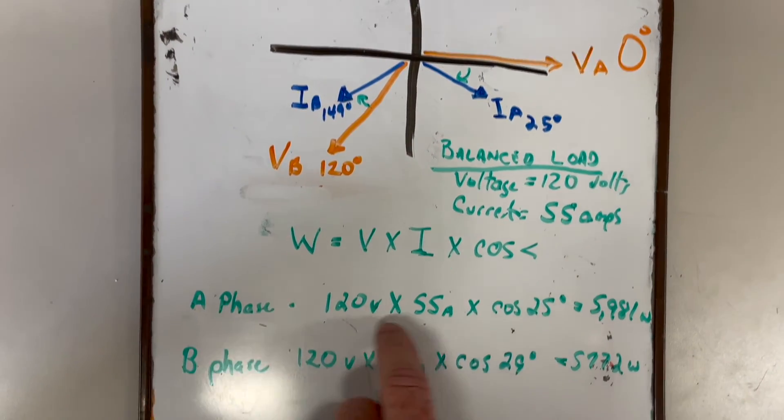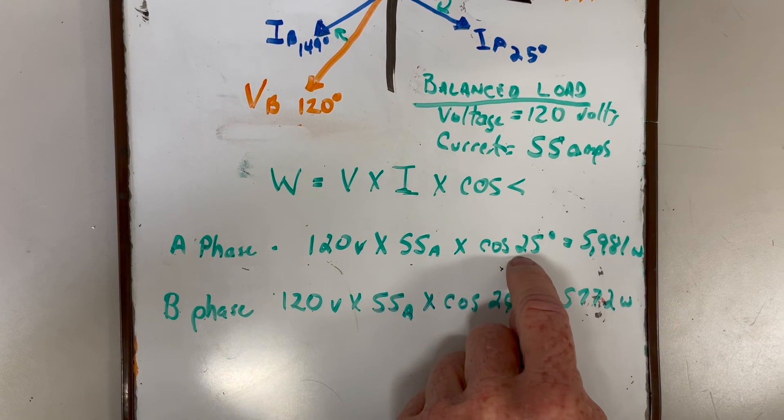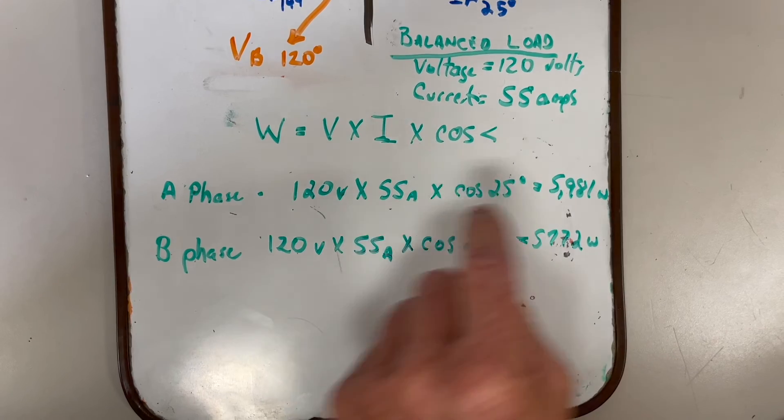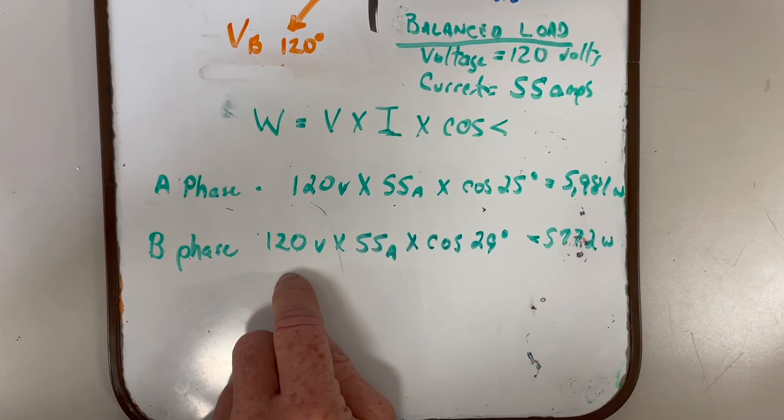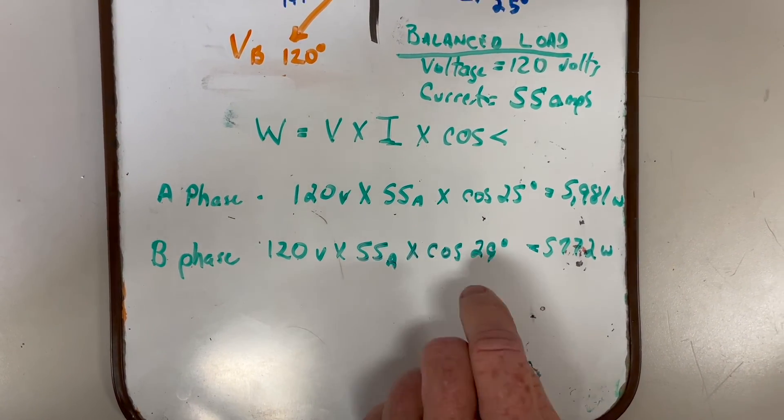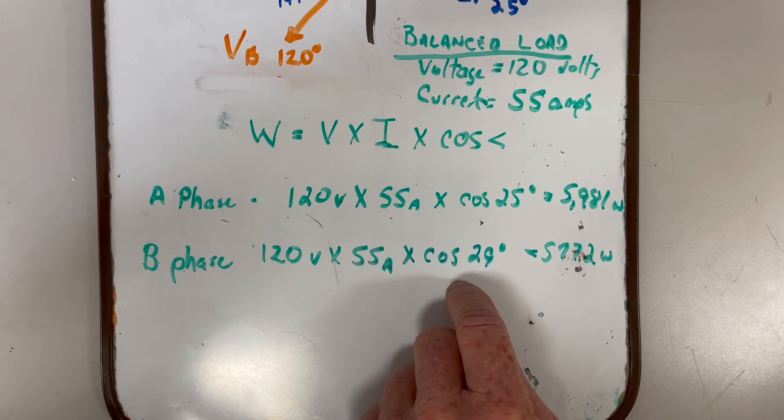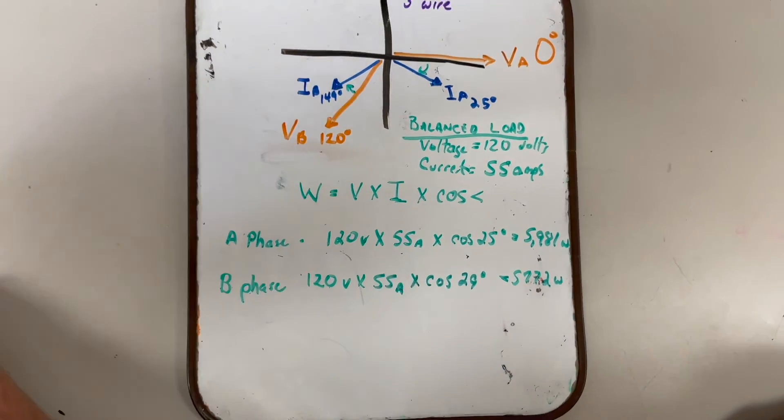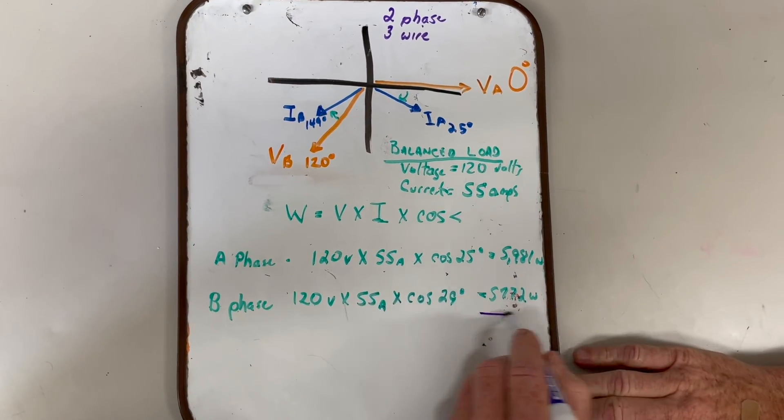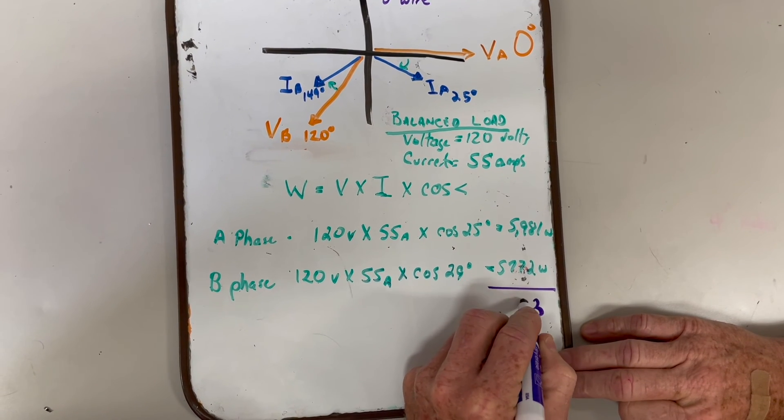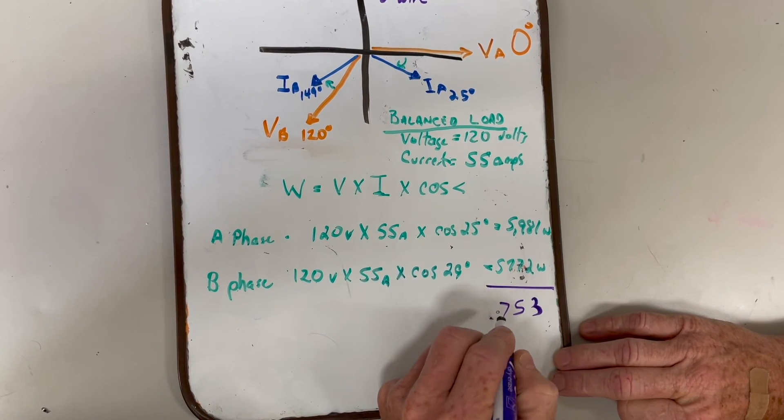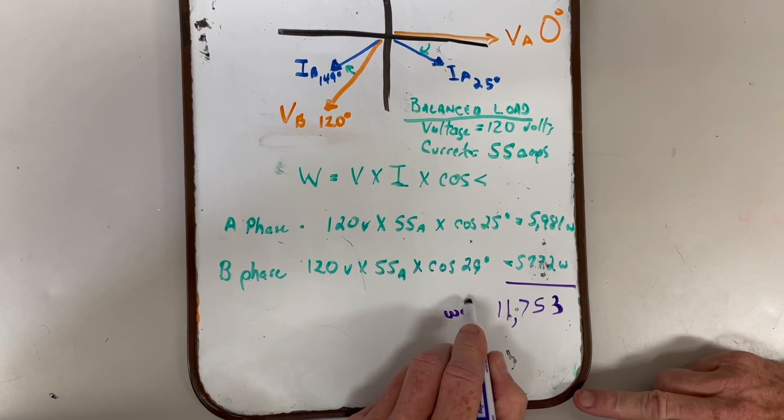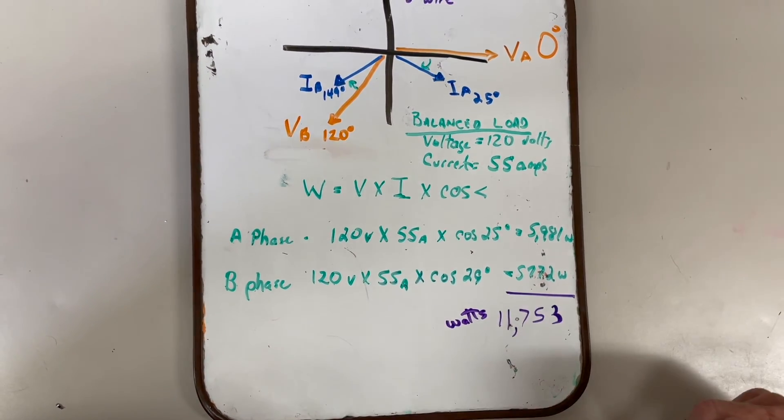So what we wanted to figure was the watts. What we do is for A phase we take 120 volts times 55 amps times cosine of the angle and we got 5,981 watts. For B phase we take the 120 volts, multiply times the 55 amps, and times the cosine of 29 degrees and here we get 5,772 watts. So we could total this up and we'll get 11,753 watts total power being used at this site.